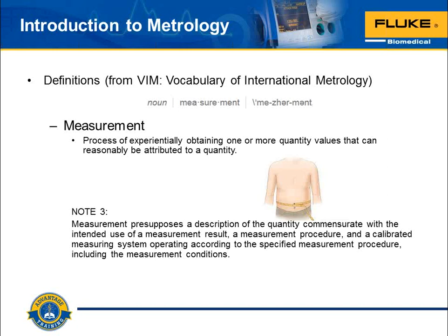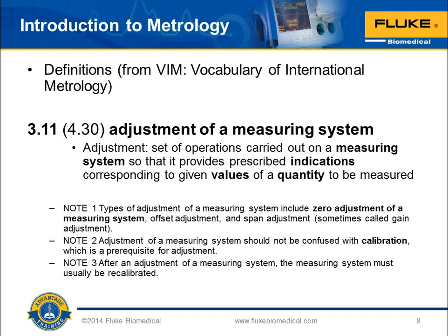The adjustment of a measuring system, we should never confuse calibration with the adjustment that we make to the parameter to bring it back into its tolerance. That adjustment is a corrective action. It is because we're making that corrective action because we have made a calibration assessment or measurement and analyzed that compared to its primary standard, and we have determined that it is not within the tolerance that we want it to be. Therefore, the adjustment is a corrective action. So don't confuse this. We do this all the time in the United States where we say calibration and we're thinking the adjustment. It's not the adjustment. The adjustment is the corrective action that follows the resulting measurement.